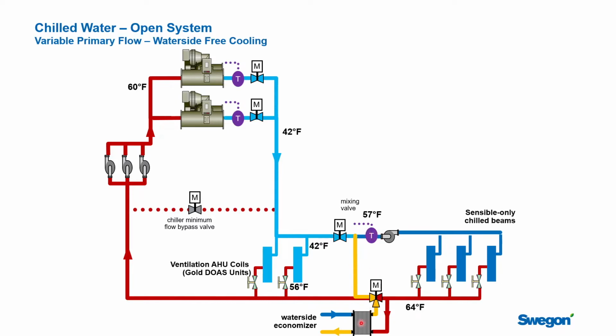So alternatively, what we'd like to do is to add a waterside economizer, a heat exchanger here. You are going to want a heat exchanger. This is going to be a cooling tower loop. It's going to be open. That water is going to have water quality work that has to be done. You want to separate it from your clean water that's inside the building.